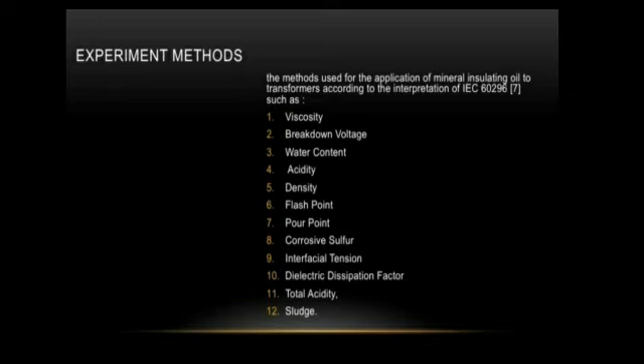Number 10, the dielectric dissipation factor. The parameter is very sensitive to the presence of polar contaminants, aging products or colloids, and sediment in the oil. Number 11, total acidity. The ability of the new insulating mineral oil to resist oxidation at elevated temperature in the presence of oxygen and copper catalyst is called oxidation stability. Number 12, sludge. The test distinguishes between sediment and sludge.